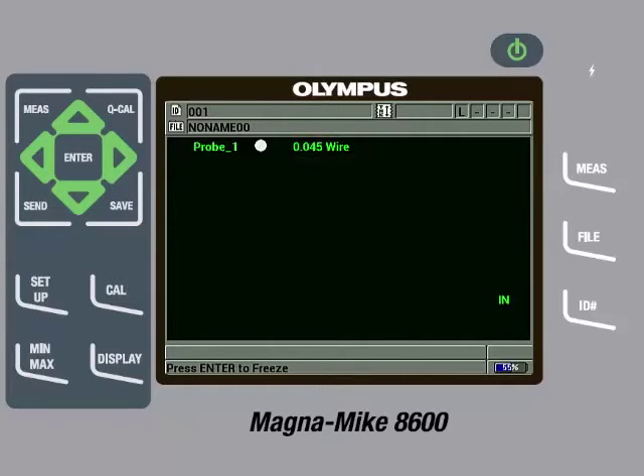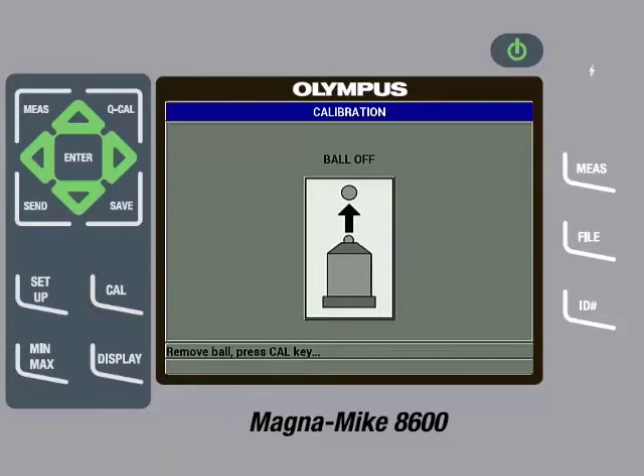Before beginning to calibrate, it is good practice to make sure the wear cap on the probe is screwed on securely and the instrument is in an environment with ambient temperature that is free of magnetic interference. The instrument should be in the location that it will be used in on a regular basis. We can now calibrate. To initiate the calibration process, press the Cal key. The first step of calibration is to perform a ball-off. To do this, make sure the wire is removed from the probe tip, then press the Cal key.